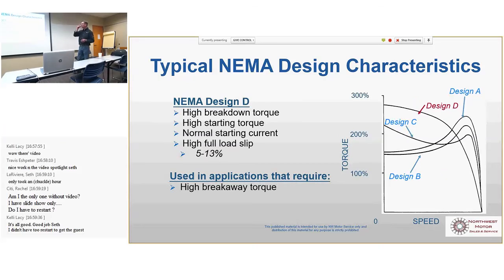The last one is NEMA D. NEMA D is the highest starting torque, up around 300, 275 typically, and its curve just drops off like that. These are elevator motors. You see these a lot in elevator motors. Some centrifuges, things like that. Again, really high inertia, really high.